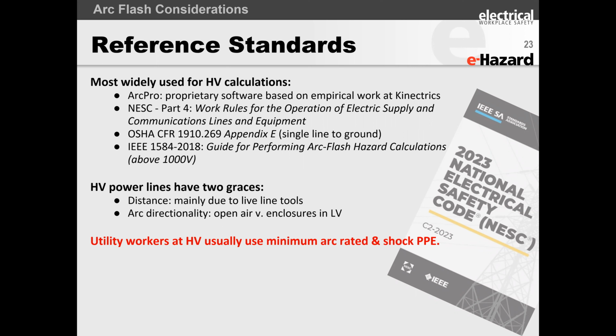The other factor that we've got, and this is a big one: when you're outside, in an open environment, arc directionality is very important. So you may have an arc flash and only part of the fireball engulfs you. Most of the core of the arc maybe moves in the opposite direction. Hey, but if you've got bad luck like I do, trust me, that arc's going to chase you and land up on you. All right. So obviously we never take a chance with this. So utility workers at high voltage use the minimum arc rated and shock PPE. Why am I making such a contentious statement? Because folks, for all of the arc flash studies that we have done on transmission lines and high voltage distribution yards, etc., because of the way that the protection is set up and because of the increased working distance, they will get out to an 8 calorie or a 12 calorie per centimeter squared ensemble and would be adequately protected.